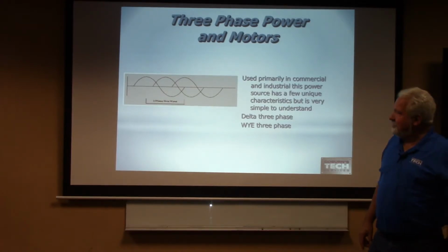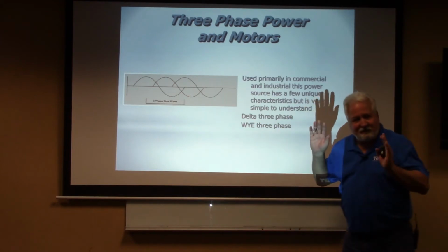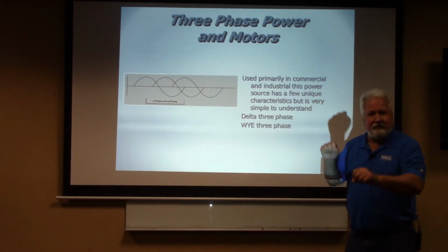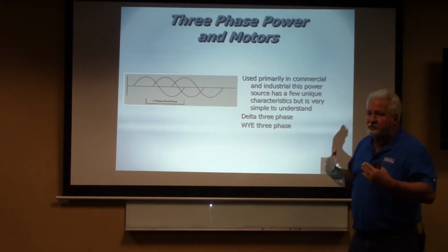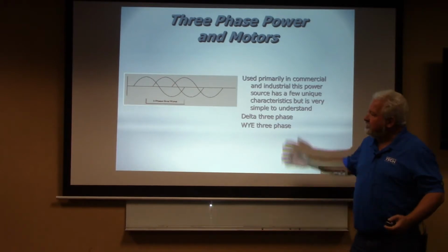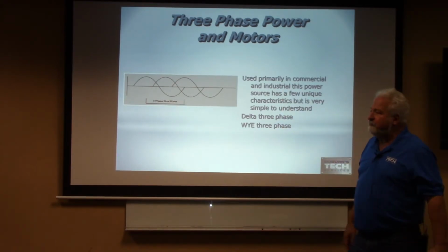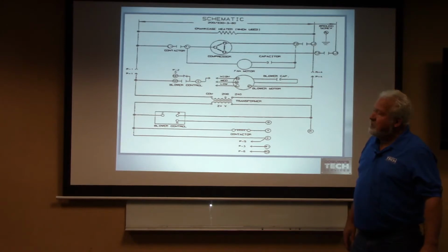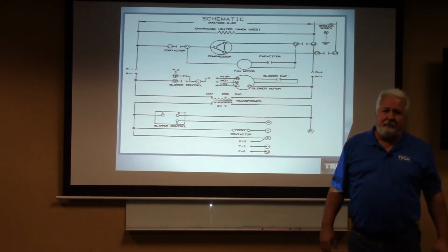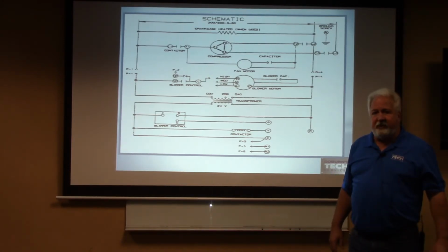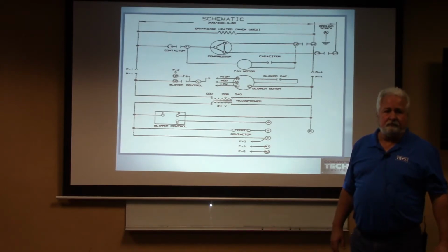If I had a third phase that I could push that pedal, it would make everything operate a lot more efficiently, a lot more smooth. Is that making sense? Good. So our starting torque on our three-phase is going to be very, very high. Can we have a three-phase compressor with a single-phase fan motor? Let's take a look and see.